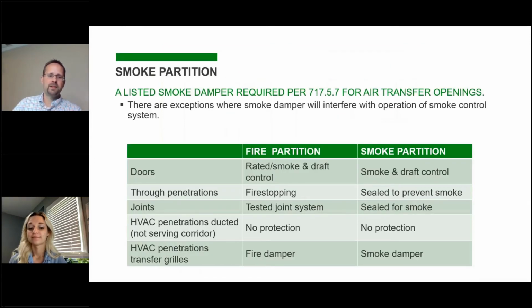So the biggest thing with smoke partitions is that dampers are only needed for air transfer openings. In a smoke barrier, whether you have a fully ducted supply or return or not, the smoke dampers are required, barring the exceptions that we mentioned before. But for a smoke partition, no exceptions are needed for a ducted system. So if you're penetrating a corridor with a smoke resistive wall in a ducted system, like into a patient room, you don't have to have dampers at each of those penetrations. But if you're in some facility where you happen to have plenum return for whatever reason, and you had a smoke partition and you had transfer openings, you would need a smoke damper at those transfer openings.